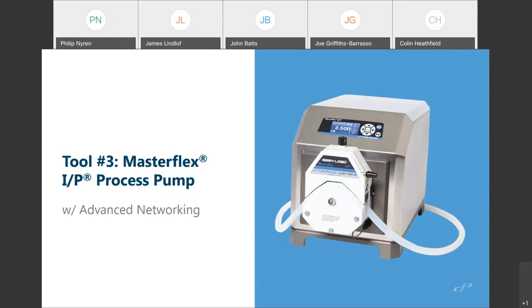If you look at this drawing, you see there's a small little wire sticking out to the pump head. It has what we call an open head sensor, so that if someone opens the pump head, it will tell the pump. The pump will tell your system via the advanced communication. This means, one, it stops the pump, so it's a health and safety supplement. And two, it means if your process is interfered with by someone accidentally opening the pump head, it will tell your system. This is all part and parcel of this two-way communication from the system to the pump and the pump to the system.